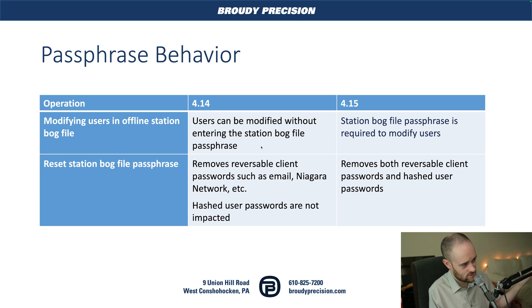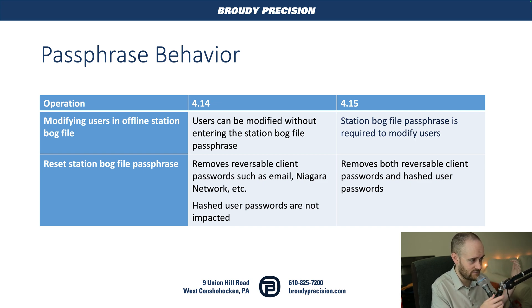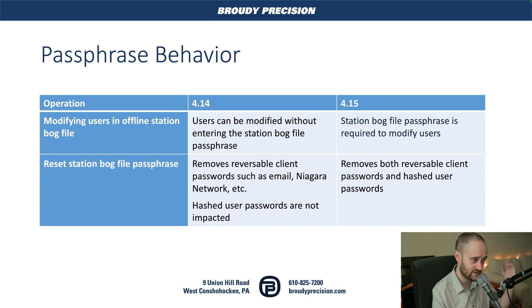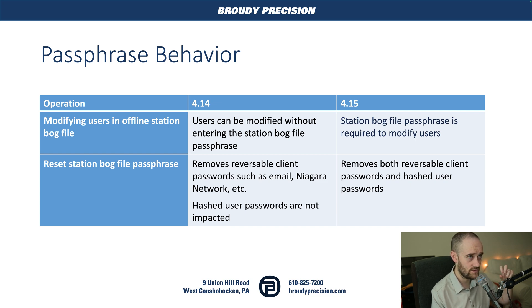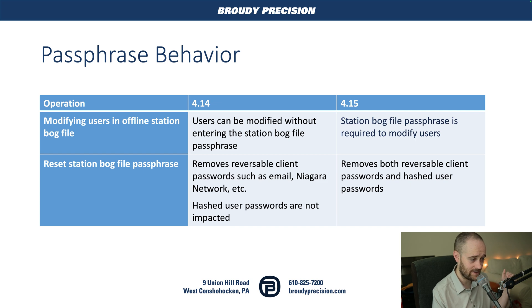To briefly go over this again: the way passphrase behavior has worked in 4.14 — if you want to modify a user in an offline station, you can do that without entering the passphrase to save. And the same thing for resetting. Because there's no encryption on the users, when you go to reset a station passphrase, it only removes the reversible passwords that have been encrypted using that passphrase — like email passwords and Niagara network passwords — but user passwords won't be affected.